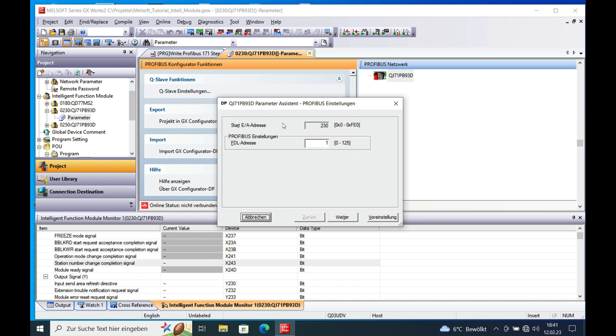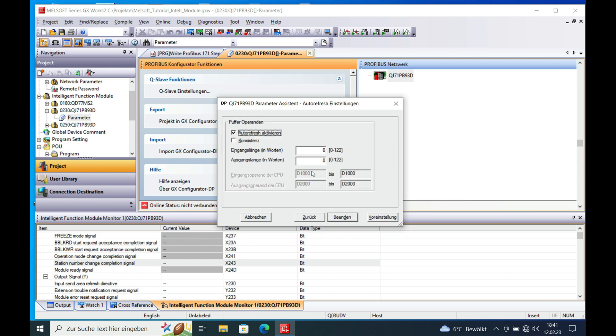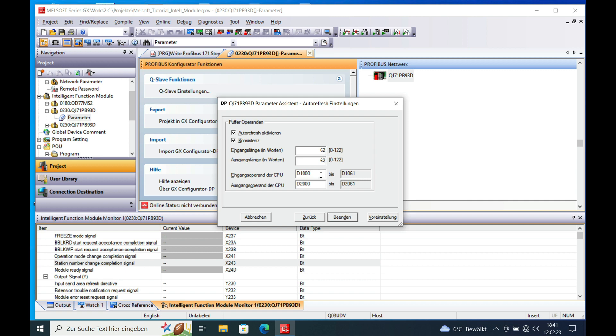Which means you have to put in your start address from 0 to 125. If you got that done, click on continue and check on the auto refresh and also the consistent data. And put a length in of the words that need to be sent and received. In my case it is 62. Send and receive and then you are all set.